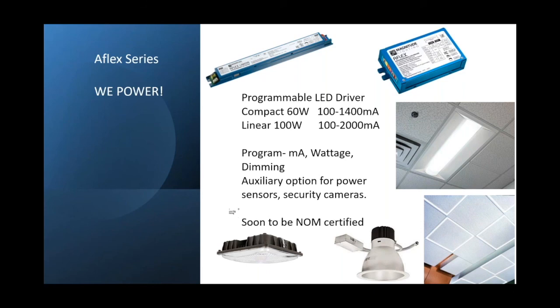Another feature our Aflex offers is an auxiliary option, which allows it to power up sensors, occupancy sensors, security cameras, anything working with 12 volts or 24 volts that needs to be powered in that space, whether it's a conference room or a cooling fan for refrigeration. This is a driver that can already be installed into the light fixture, but also serve a secondary purpose of powering up that aux sensor.